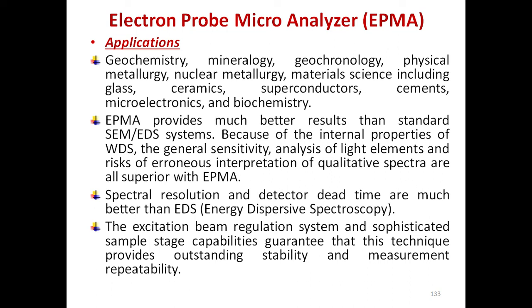Because of the internal properties of WDS, the general sensitivity, analysis of light elements and risk of erroneous interpretation of qualitative spectra are widely superior to EDS. With EPMA, spectral resolution and detector dead time are much better than EDS. The excitation beam regulation system and sophisticated sample stage capabilities guarantee that this technique provides outstanding stability and measurement repeatability. This ends the electron probe microanalyzer.